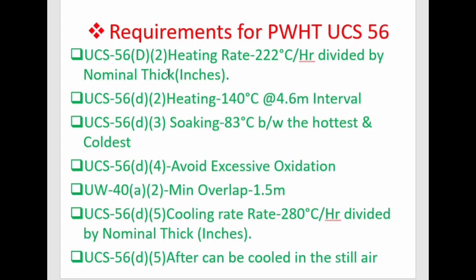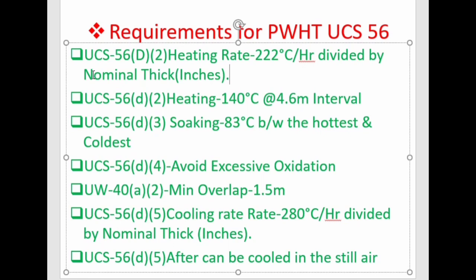Moving into the requirements for PWHT as per UCS-56 of Section 8 Division 1: the first requirement is the heating rate, given in UCS-56 D2. It states that above 425°C, the rate of heating shall be not more than 222°C per hour divided by the maximum metal thickness of the shell or head plate in inches, but in no case more than 222°C per hour. To find the heating rate, divide 222°C by the nominal thickness of the vessel in inches.